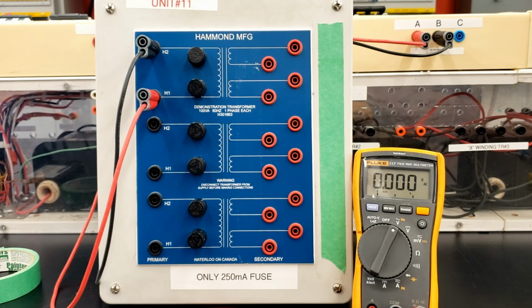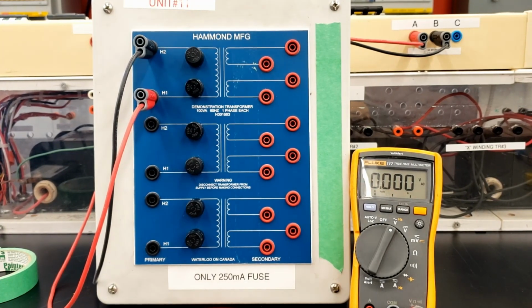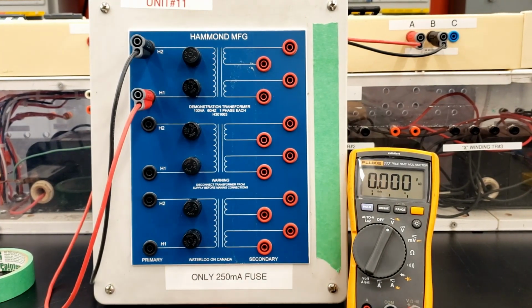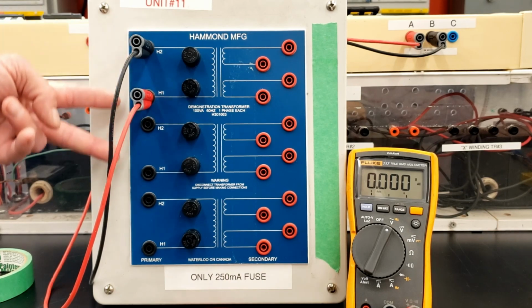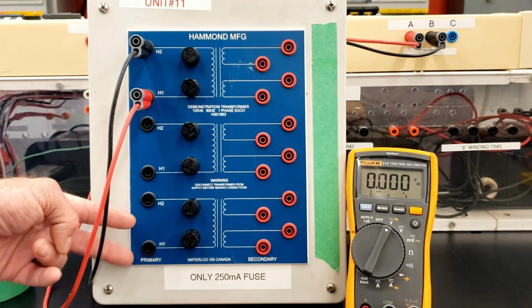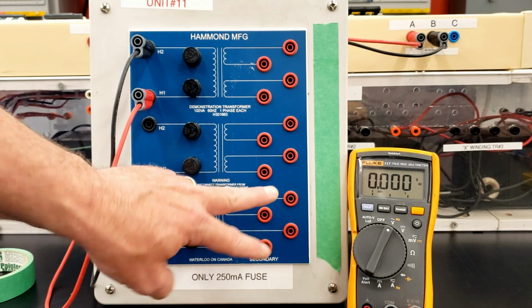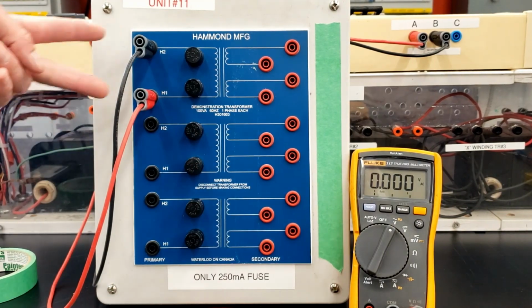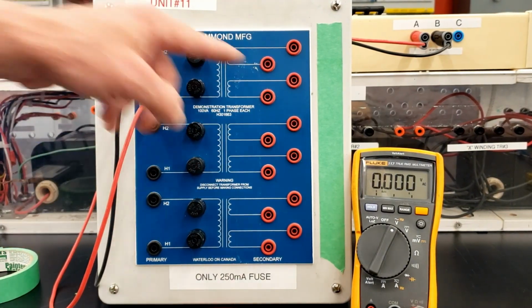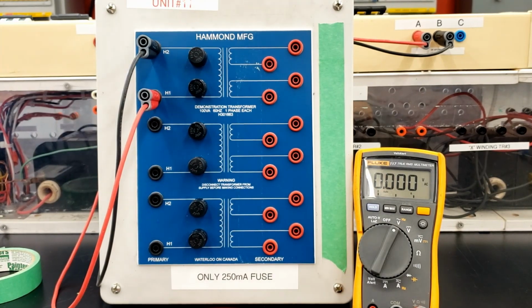We're going to do this buck boost, or additive-subtractive, test on each of the transformers. It's essential that you keep this polarity the same for each transformer. If you flip that polarity, then all your secondary polarities change as well. So keep this polarity the same so we can mark out X1, X2, X3, X4.